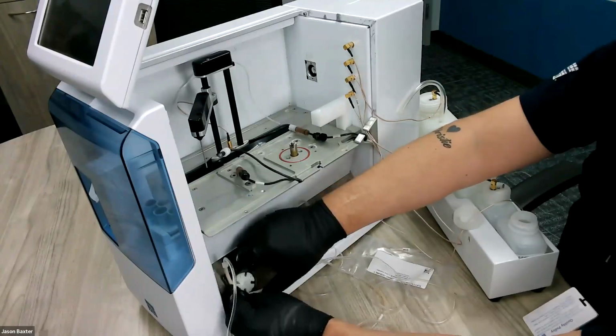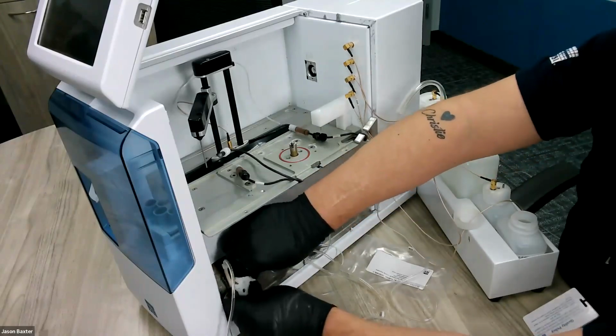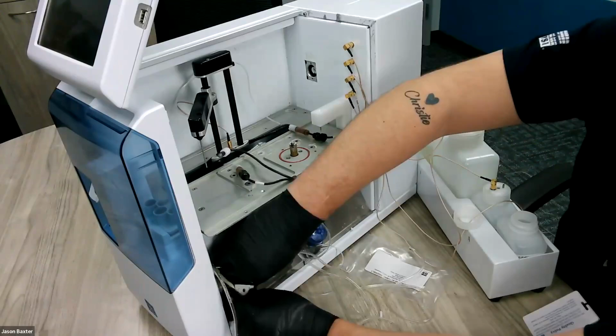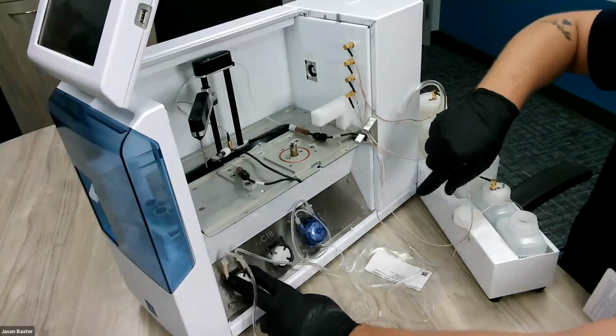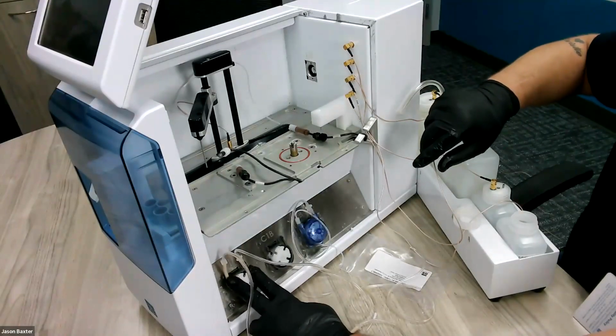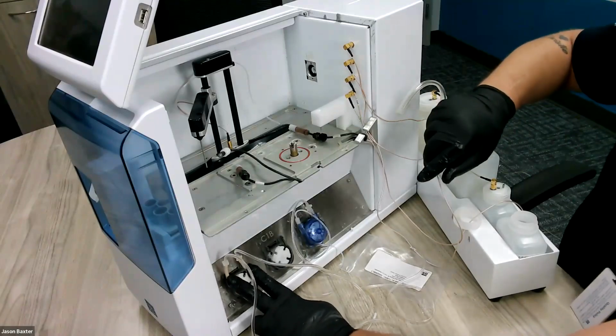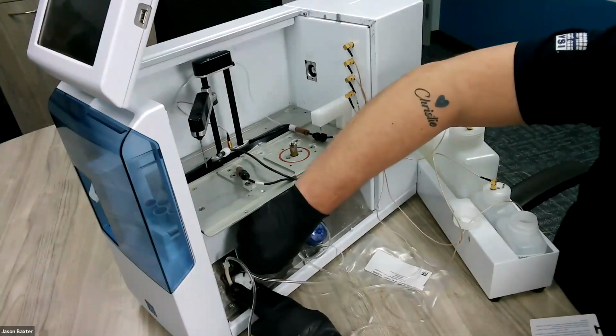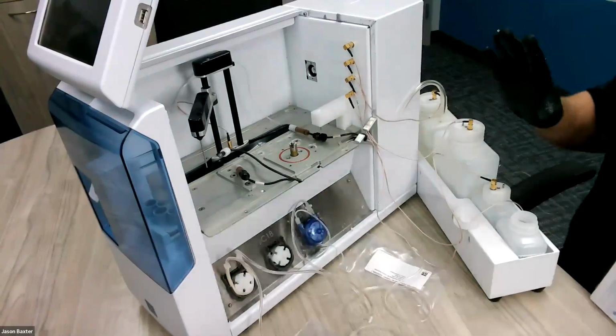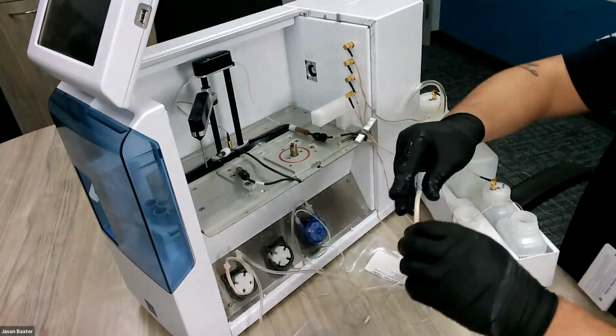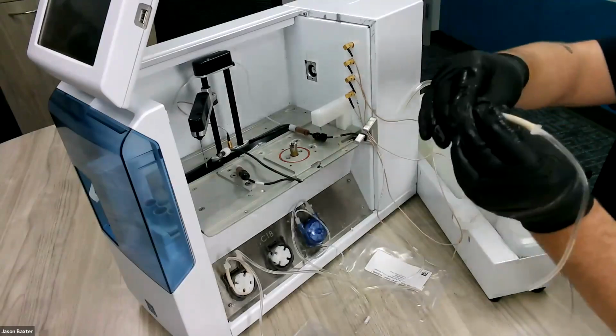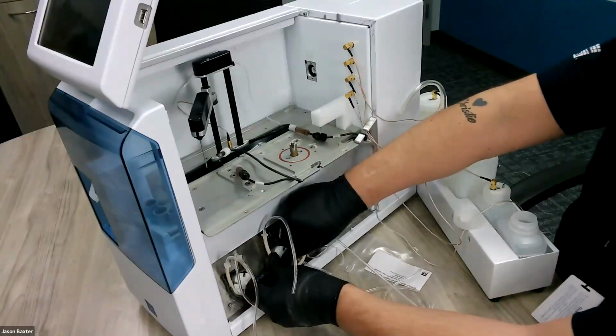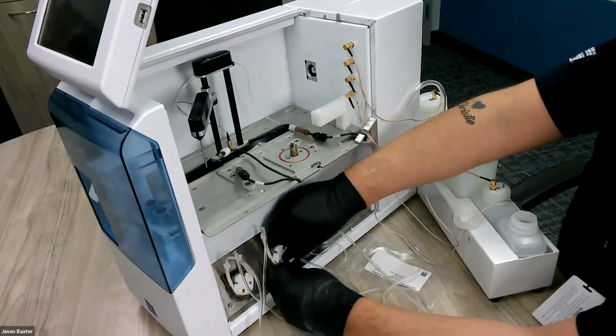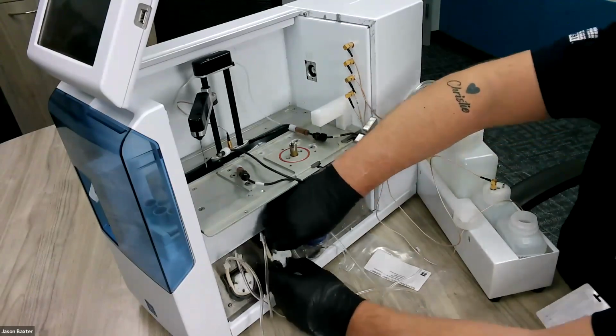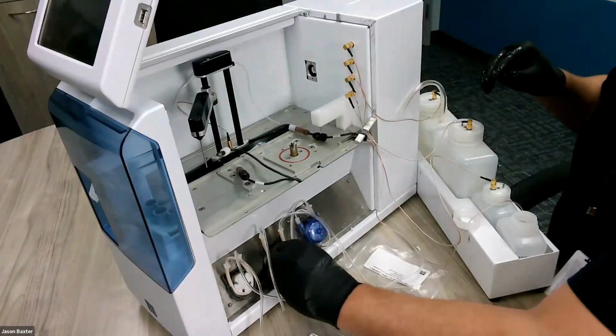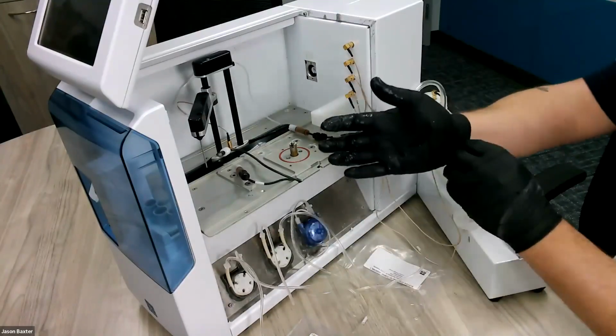You'll notice the calibrator lines are a bit longer than the buffer line. This is by design. What I look to see is that these two ends of the tubing that are coming up out of the top of the pump are roughly at the same height. As long as they're close to the same height, you'll be just fine. We're going to do likewise with B. There we are. Now at this point is when I'll usually take my gloves off.